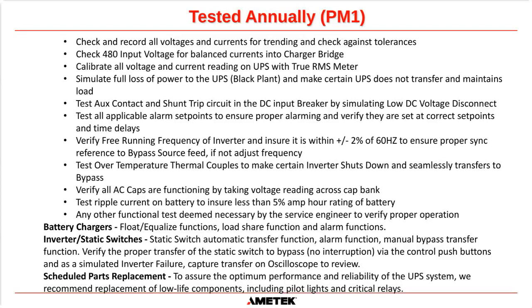We test all applicable alarm set points to ensure proper alarming, and then we verify that they are set at the correct value and time delay, and we will make sure that they repeat at your DCS system in your control room. So we would appreciate it if, when our guys come out and we're testing the alarms, somebody has radio contact with the control room and asks, has this alarm come in and do you see it at the control room?